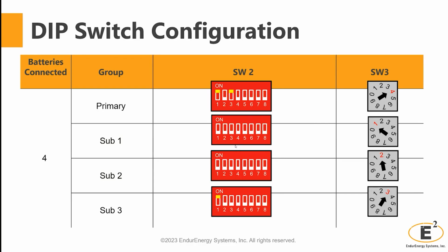These configurations are super critical because usually when doing troubleshooting, sometimes when you get communication faults, those can be fixed just by looking at the DIP switch configuration and making sure you have the proper setup.